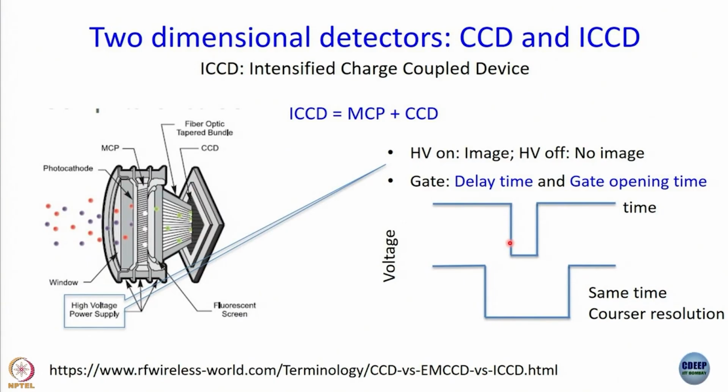Earlier, maybe 20-25 years ago, the best one could do was nanosecond. But sometime towards the beginning of the 21st century, cameras like 4 Picos and PicoStar were introduced, where you could change the delay with picosecond time resolution, and apply gate times of say 50 picosecond to 20 picosecond. Now, I think you can do 20 picosecond also. So, with the improved electronics that is available now, this is becoming a better technique to do time resolved measurements.